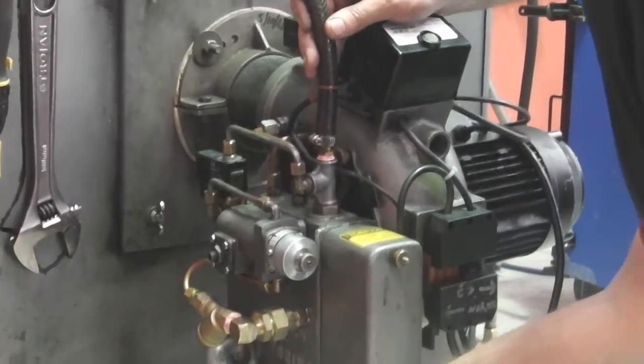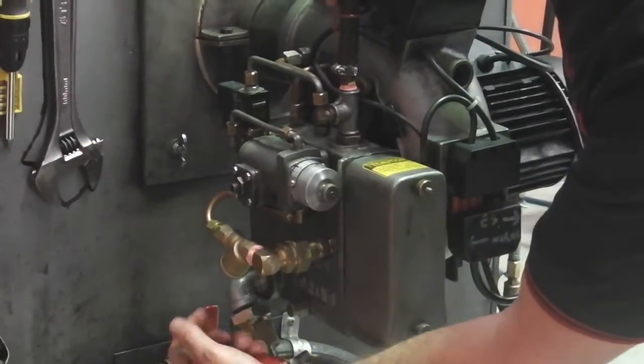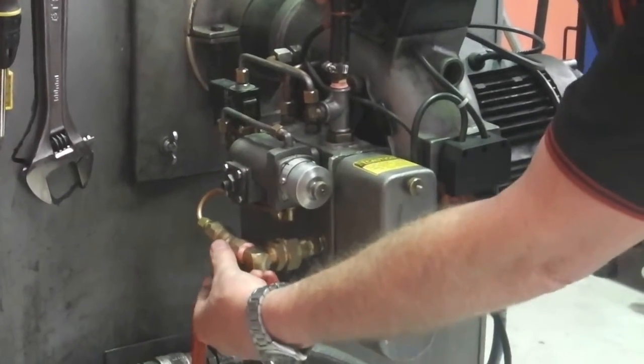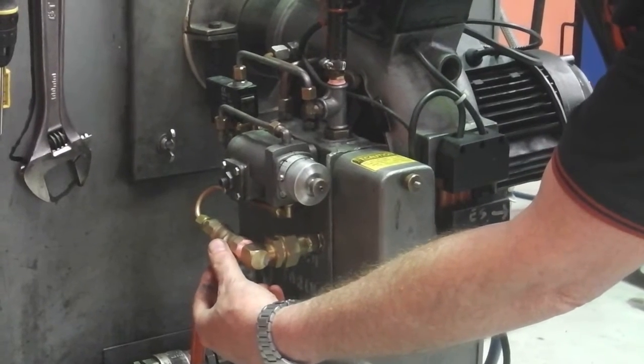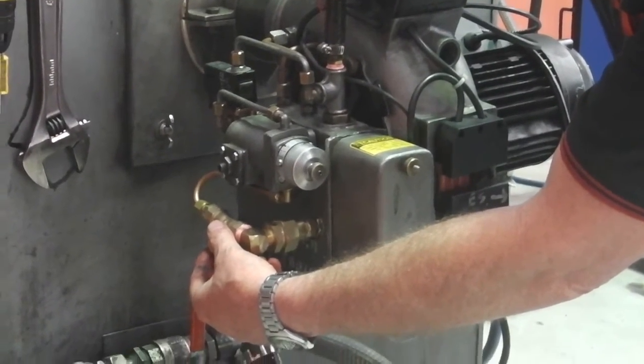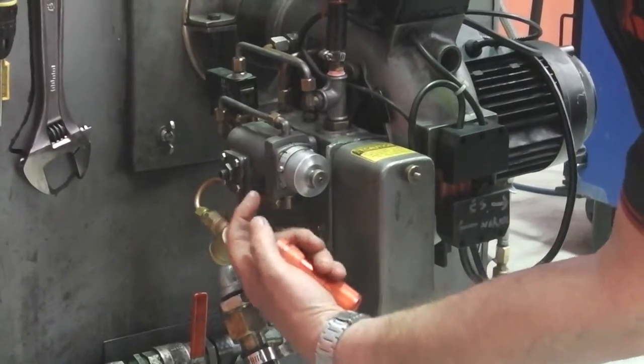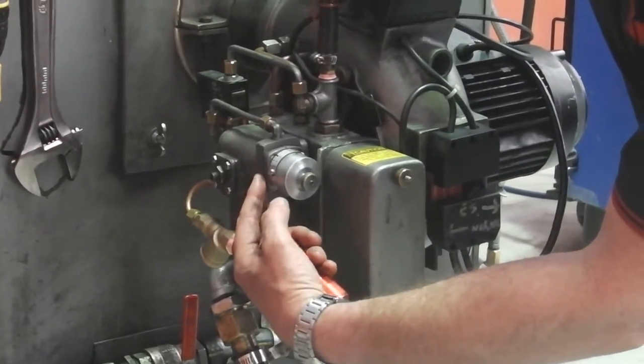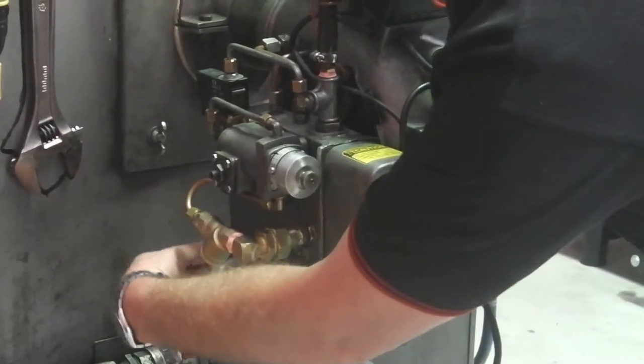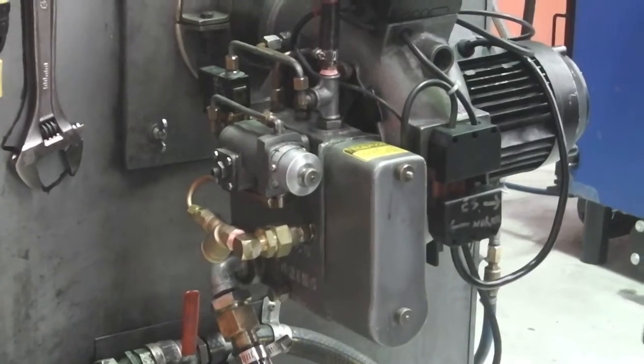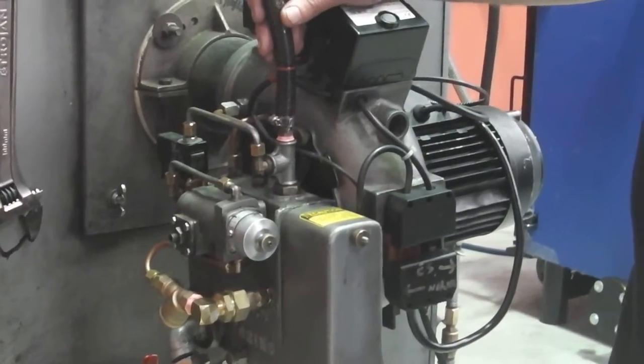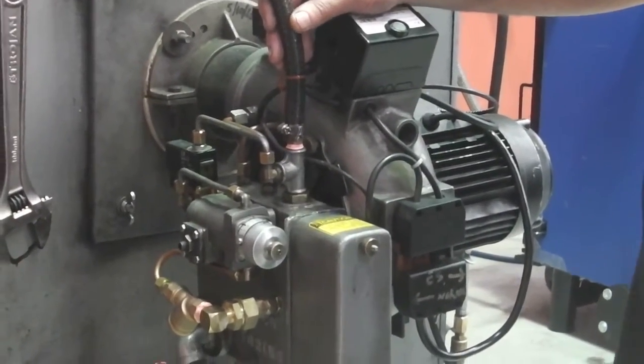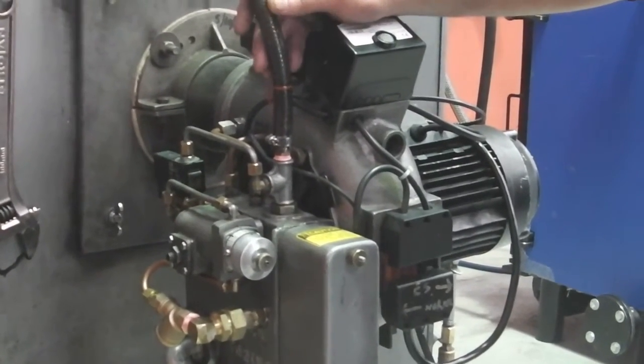Just another quick thing on the side here is the Y-Strainer, and that's like a final filter. That filters any oil that's feeding into the internal pump that's behind this silver wheel. There's also a major or a coarse strainer in the front of the burner gun. I'd suggest you look at that in the book, and that has to be cleaned every two to three months, for example, with normal waste oil.